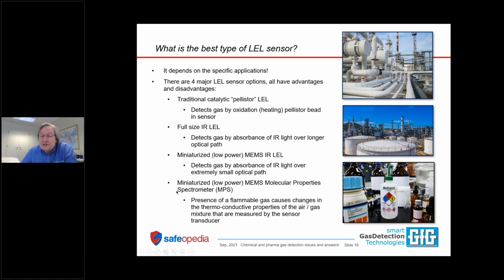Another type of sensor that we're finding in portable gas detectors is the MPS sensor. That stands for Molecular Properties Spectrometer. And these detect gas by looking at the difference of the density of the gas in the affected area versus the density of fresh air. So lighter than air combustible gases like methane will have lower density, and you can tell the difference. Heavier than air combustible gases like propane and pentane and alcohols are heavier than air. So again, you have a detectable difference in the density compared to fresh air.